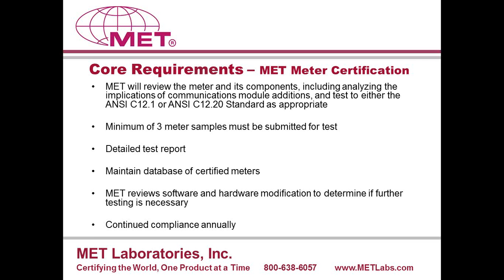So, of course, we're giving a detailed test report at the end of the test program. That test report is going to have all of the details of the test in there. We're going to detail the number of meter samples that were tested, the serial numbers of those samples, the FCC ID or the identification of the AMR or AMI module installed in those meter products, what the test configurations were going into the test program, any details per test, how the meters were set up and how they were tested, photos. All of the details are going to be in the detailed test report.